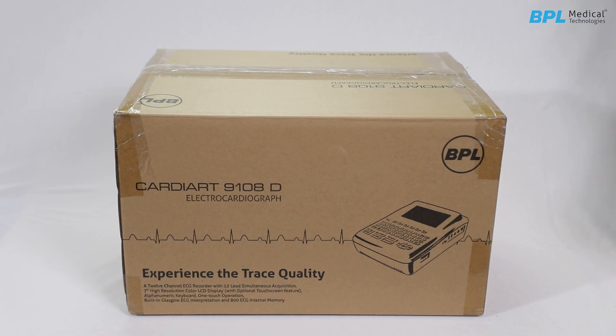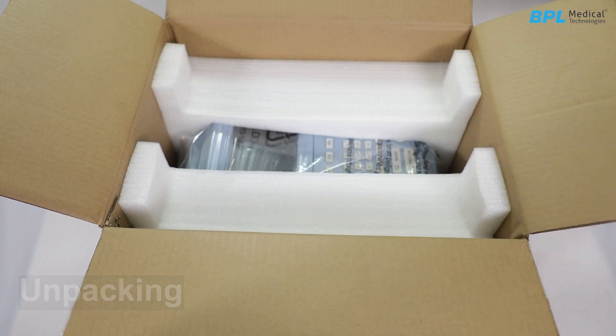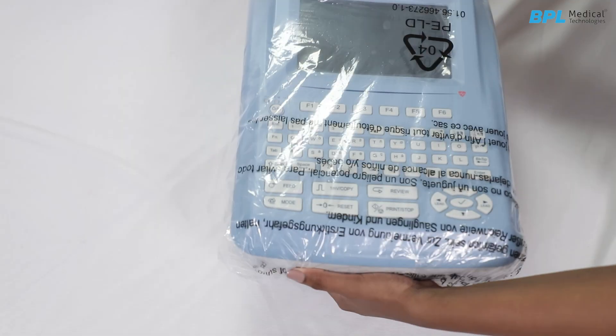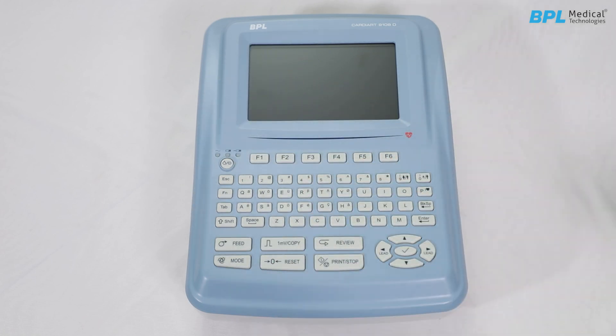Introducing BPL Cardiart 9108D. For unpacking, carefully remove the ECG unit and the accessory case from the carton box. Check for any damage to the unit. If damage is evident, please notify BPL or the service team immediately.